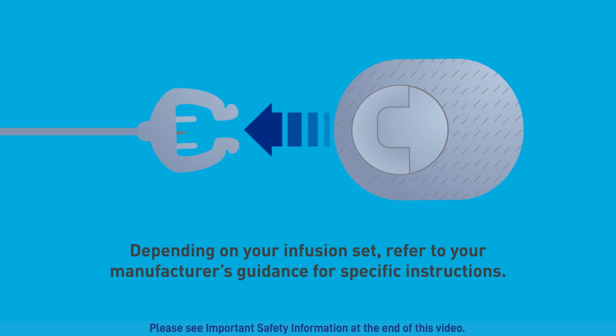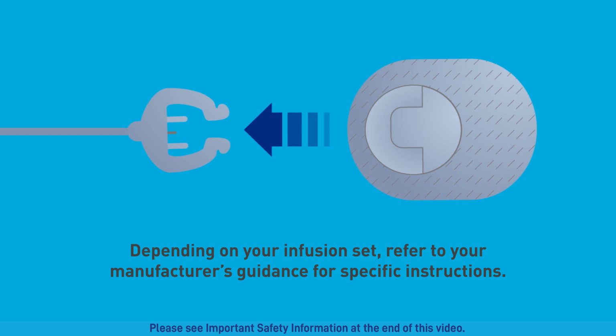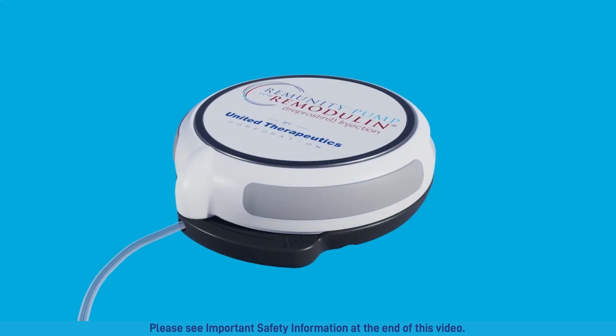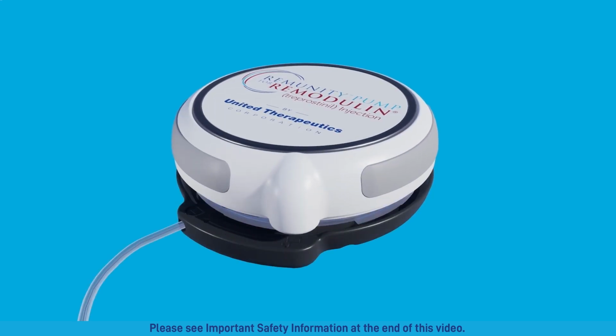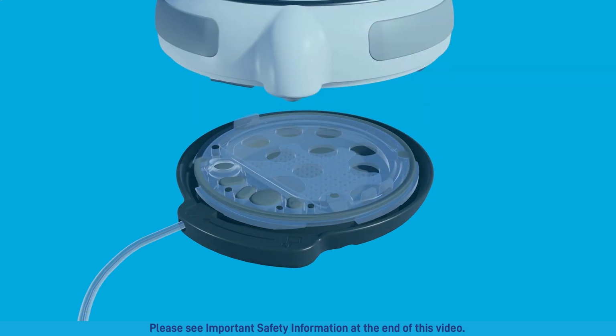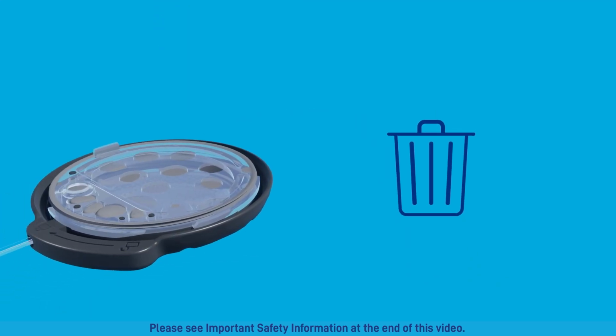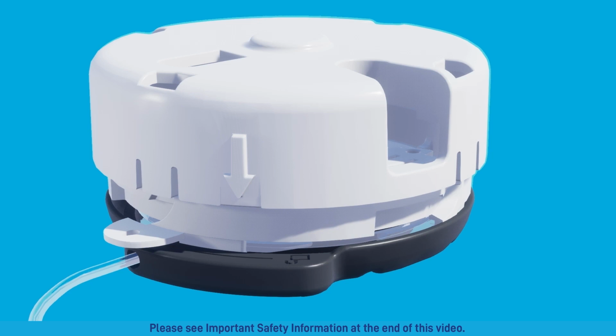Next, you will need to disconnect your current infusion tubing from your body. It is important to remember not to remove the pump from the used cassette until after you have removed the infusion set from your body to avoid unintended medication delivery. Once your infusion tubing has been disconnected, rotate the pump counterclockwise until it separates from the used cassette. Dispose of both the used cassette and infusion tubing, and you are now ready to self-fill your cassette.